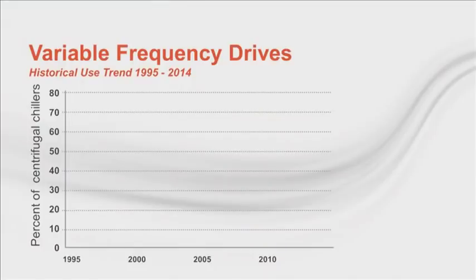Well, variable speed drives, when employed correctly, have provided a means to better take advantage of conditions that offer energy saving opportunities. In the case of centrifugal chillers, that opportunity arises when ambient temperatures allow for condenser relief. Many have and continue to incorporate VFDs in chiller design, and their use is common. However, 20 years ago, it was a much different story.